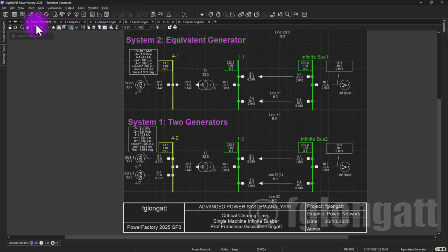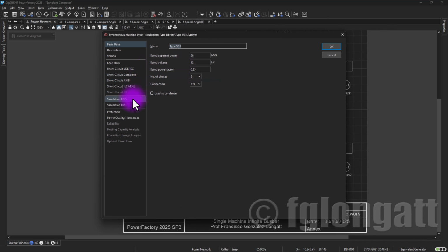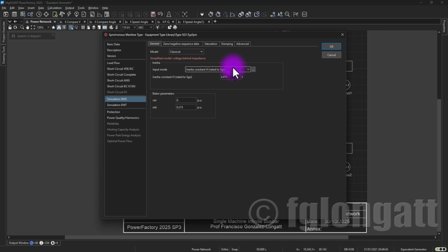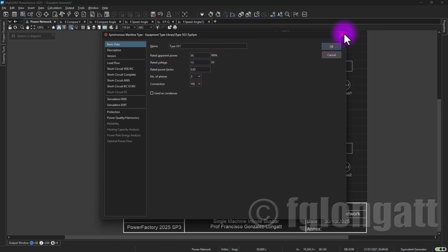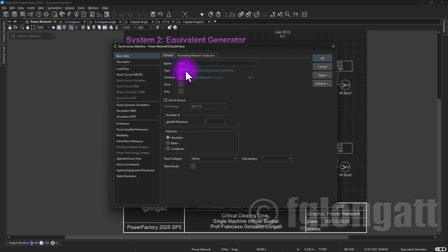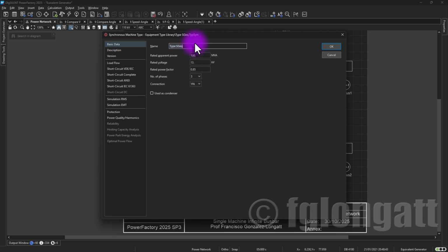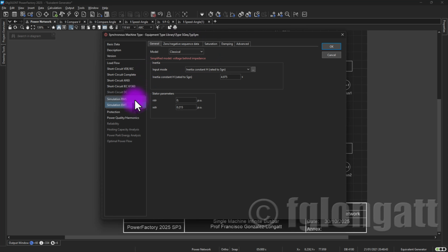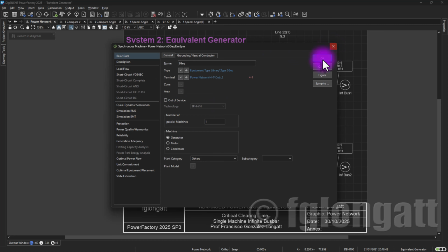So in a general sense, what I can tell you and show you is that basically if I have two generation units with inertia constant of 4.975 and reactance 0.215 and 50 MVA, I can substitute them with a single generator, and in this single generator, the rated apparent power will be 100 MVA, but you can see over here 4.975 is basically the rotational inertia, and 0.215 per unit is the stator reactance.